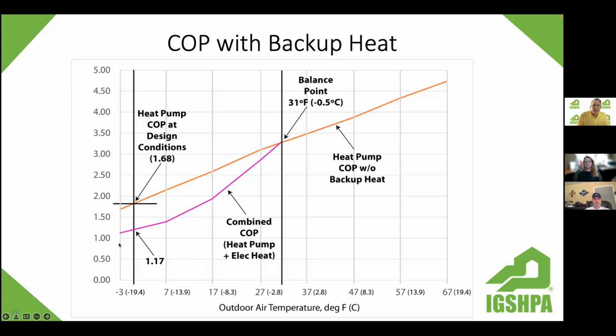Not a lot. By the time we get below -3, we probably want to shut this heat pump off, because we're just using the compressor and not getting a lot of gain. But this is something that doesn't get looked at often. We talk about HSPFs, we talk about high efficiency, and heat pumps are great. They're very reliable now. But when we actually look at capacities, we have to take a look at the combined efficiencies as well, because at the lower capacities, we need to bring in some electric heat. So we're down to about 1.17, just as a reference.